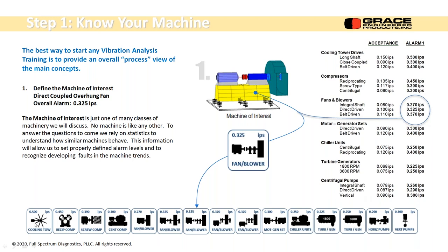We have some graphics here: cooling towers, three different kinds of compressors, five different kinds of fans or blowers, motor generator sets, chillers, turbine generators, horizontal pumps, and vertical pumps. Okay, and we get a good idea of what our machine is and what its alarm criteria is. In this case, the little icon is telling me 0.325. So I have a direct driven overhung fan, 0.325 inches per second, which is a velocity level. And it gets us in the right form for setting up our database.